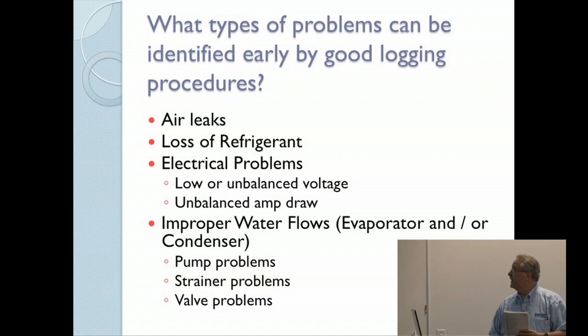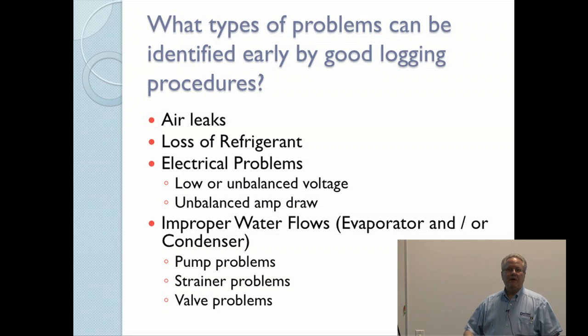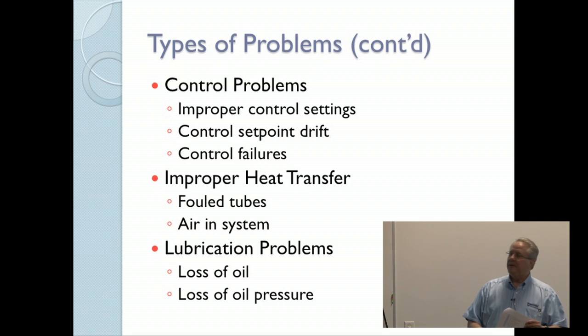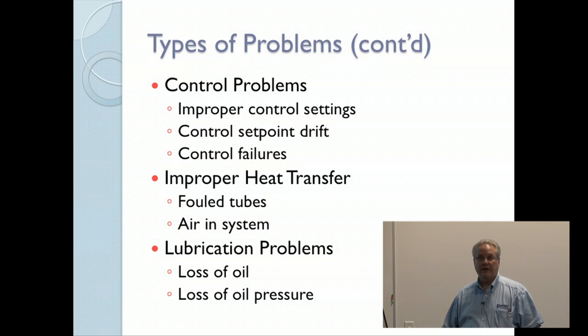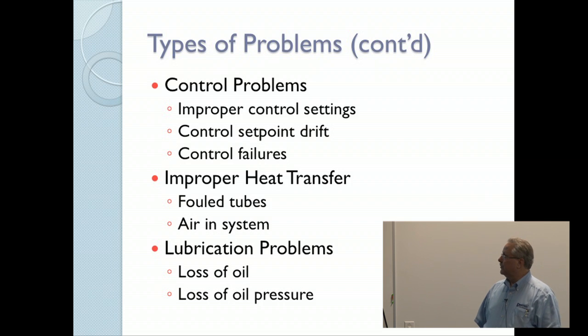What types of problems can be identified early by good logging procedures? Well, you can catch air leaks, loss of refrigerant, electrical problems, low or unbalanced voltage, unbalanced amp draws. You can identify improper water flows, either in your evaporator and or your condenser. You can see if it's a pump problem, a strainer problem, or a valve problem. You may be able to find control problems, improper control settings, control set point drift, which is less of an issue in today's microprocessor world, but nonetheless still something you have to be aware of, or control failures.